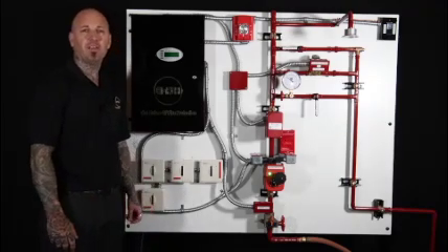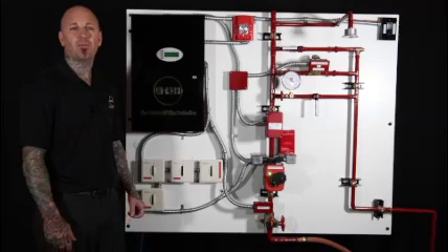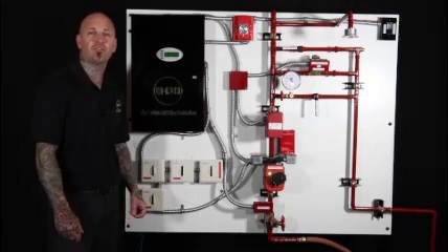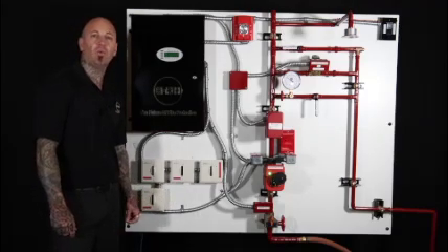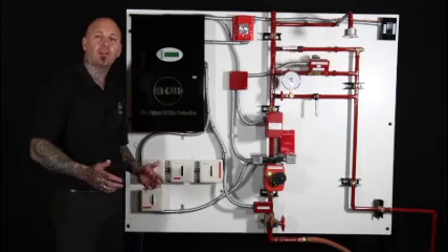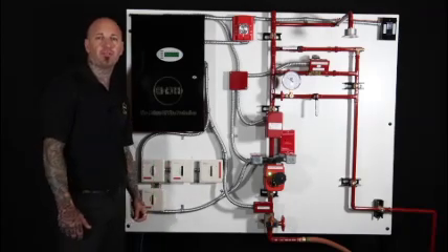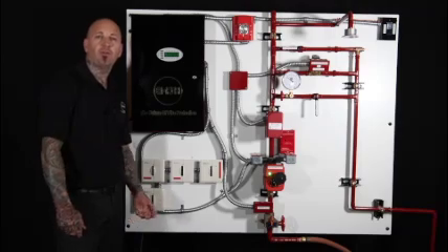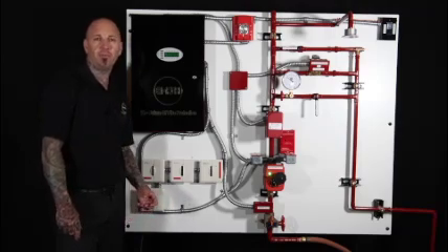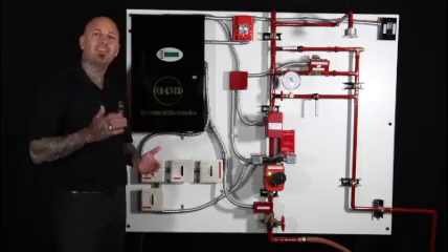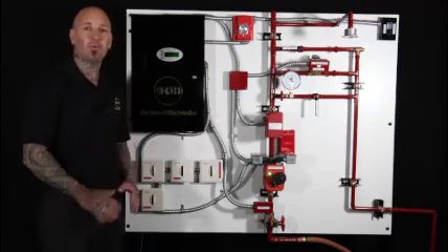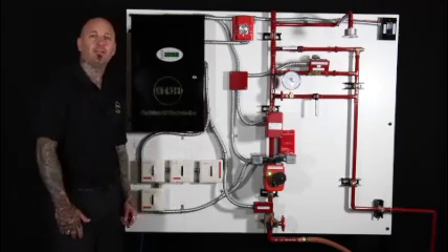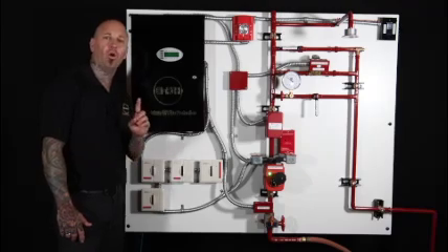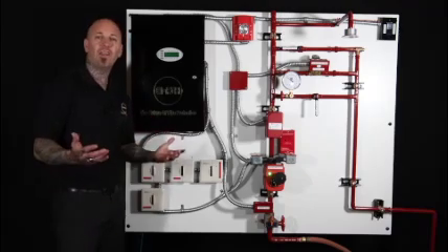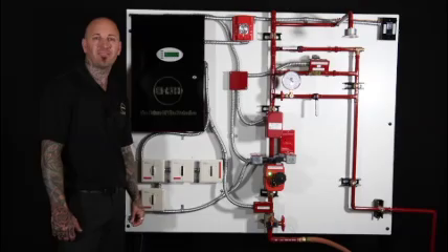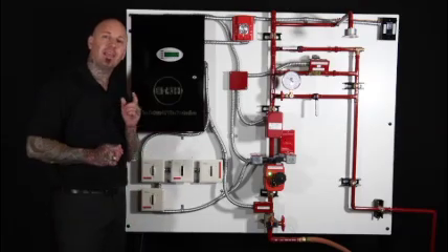For these reasons is why I knew there had to be a better way to prevent these unnecessary situations from happening, and ultimately why I came up with electronically monitored fire sprinkler heads. I've always felt there's no reason why the water should be flooding places and running for over 30 to 60 minutes when there was never even a fire. So I want you to ask yourself this one question. Why not shut the water off, right? Well, now we can, and we will.